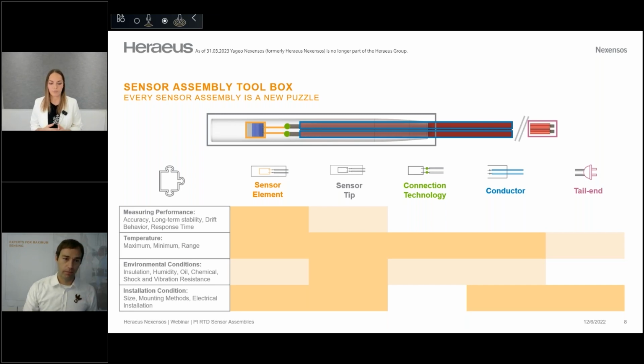It can consist of the measuring performance of the sensor. It could refer to the temperature and to the installation conditions. So let's start with the measuring performance. This consists of the accuracy, the long-term stability, the drift behavior, and the response time of the whole sensor assembly. And the sensor element has the highest influence on this measuring performance. And that's why it's indicated here in this chart in dark orange.